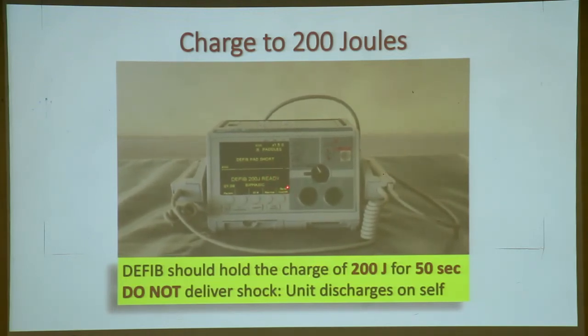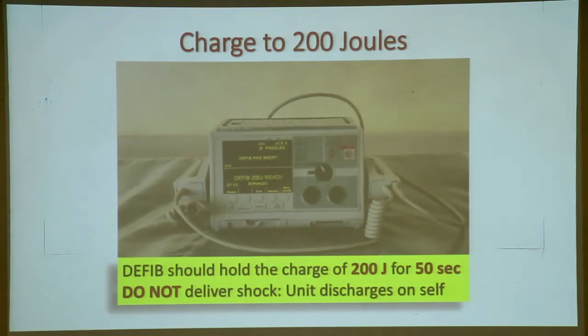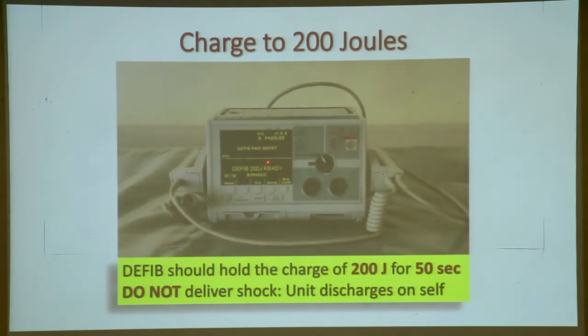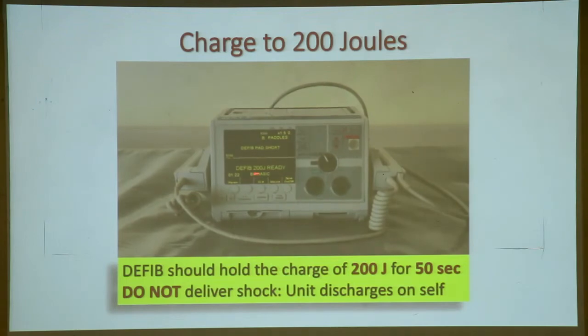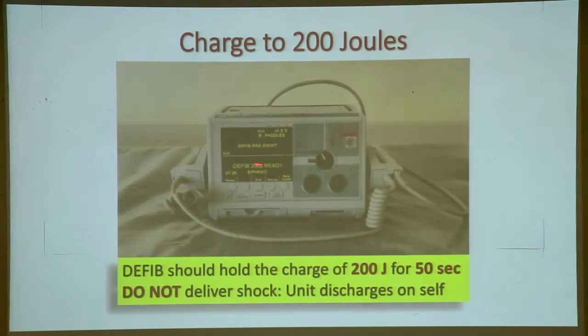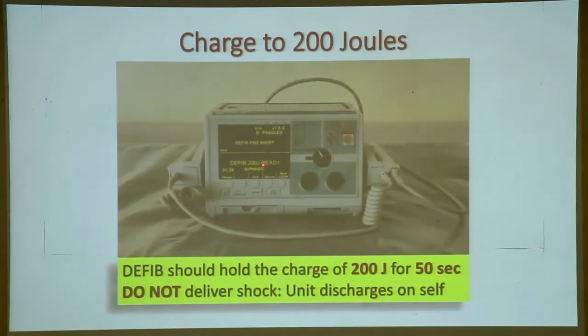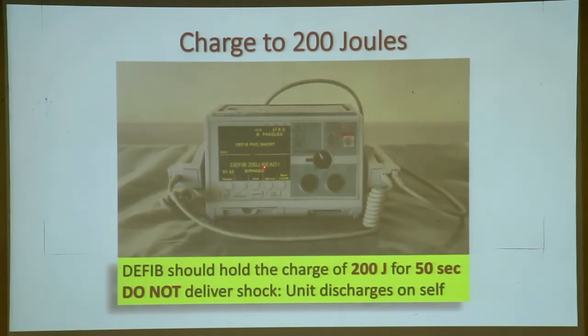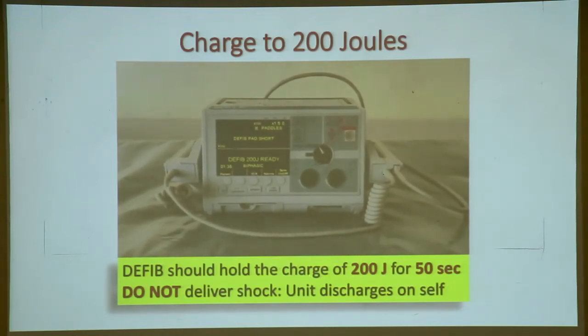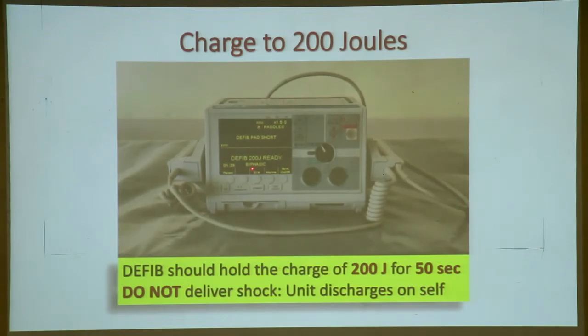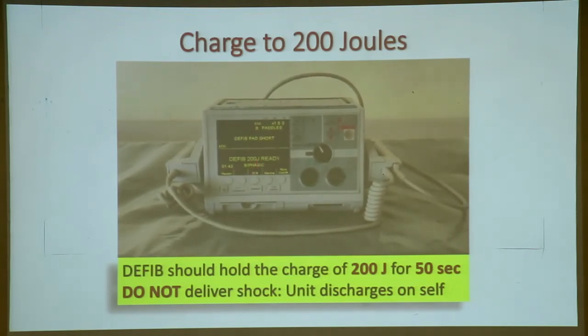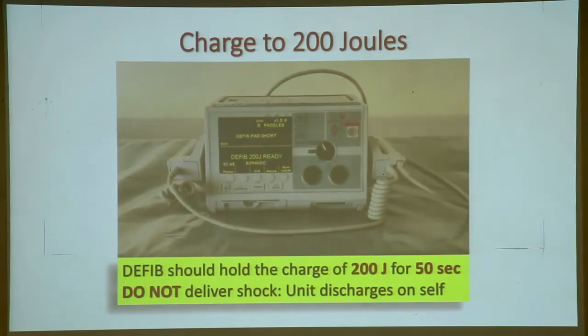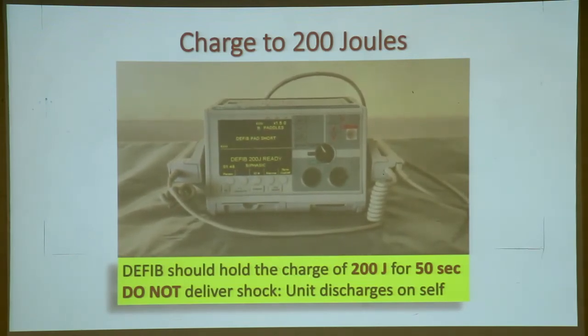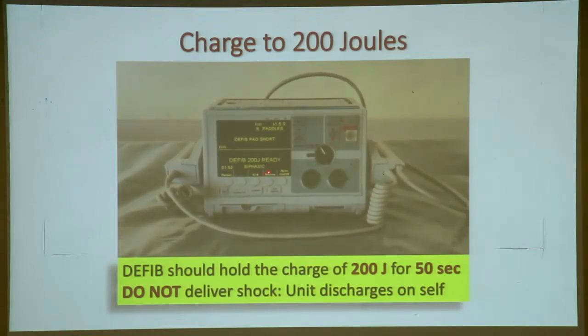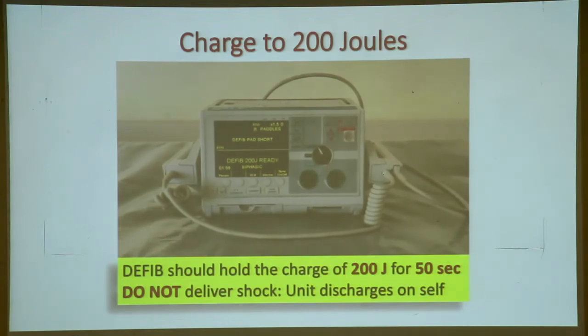I have switched off the. This noise will keep coming. The alarm will keep coming. Just keep on. Just don't do anything for it. Watch for 50 seconds. It still says 200 joules ready. So we'll just allow that 50 seconds to elapse. See, now it says. Now you get that kind of an interrupted beat, right?